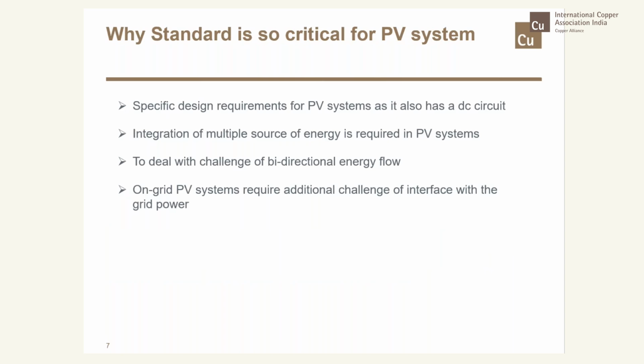Let's see why standards are so critical for solar PV systems. First, it has both AC and DC systems to design. It has to integrate multiple sources of energy coming from the solar side, battery side, and also from the grid side. Power flow can be bidirectional, as exchange of power takes place between the PV system and the grid. And finally, the power that is going to be injected into the grid has to follow certain specific protocols for its integration. It is not so easy that you just connect it and run. So at all these junction points, there are complexities. Lots of electronics, and reliability is vital, for which standards and specifications play a very important role.